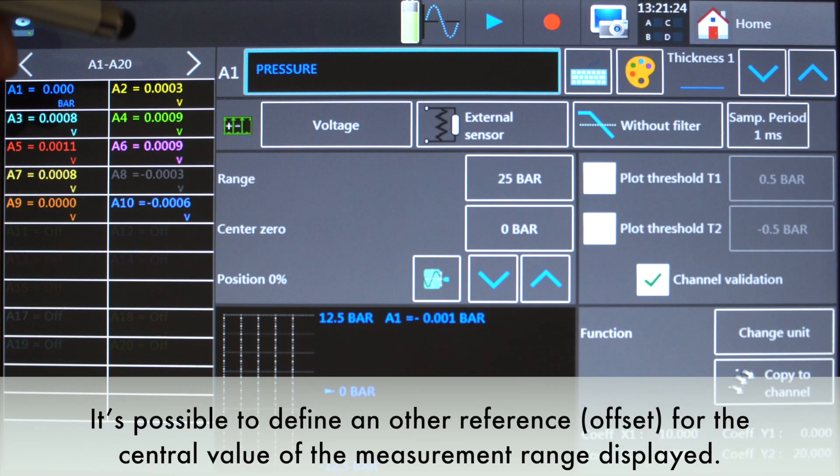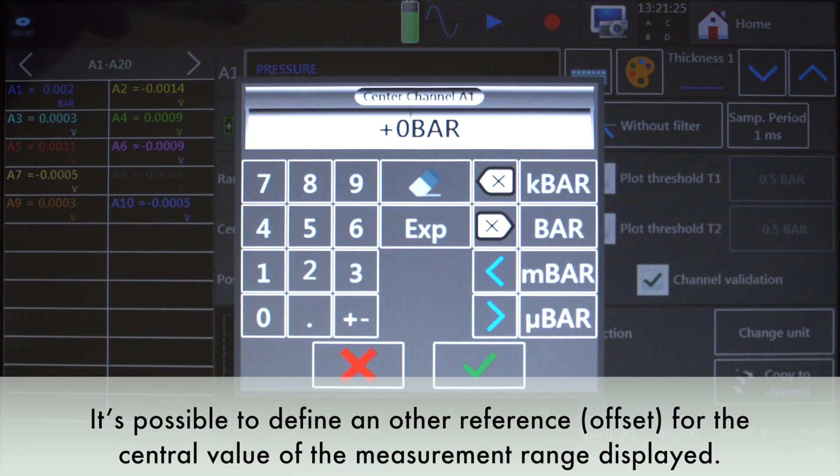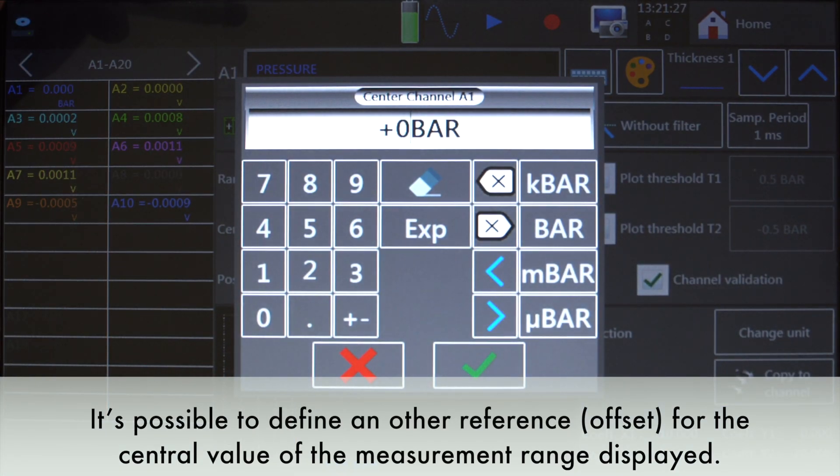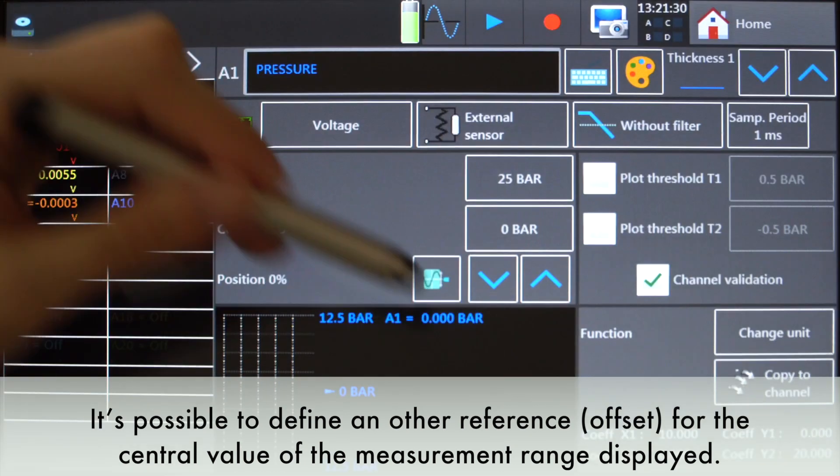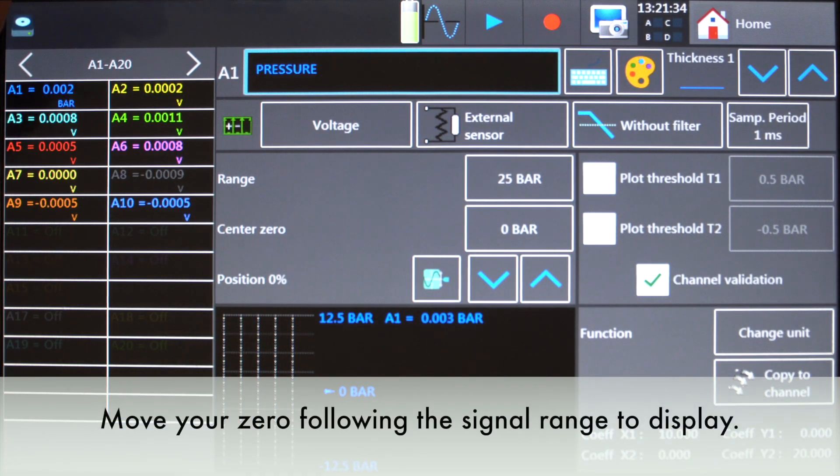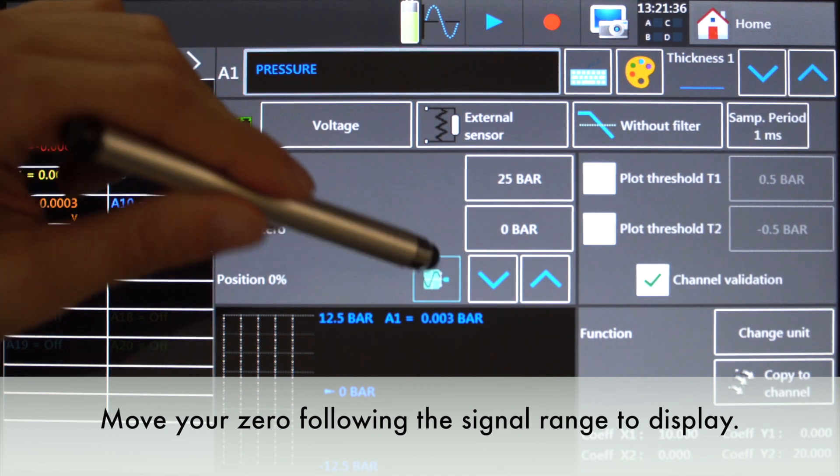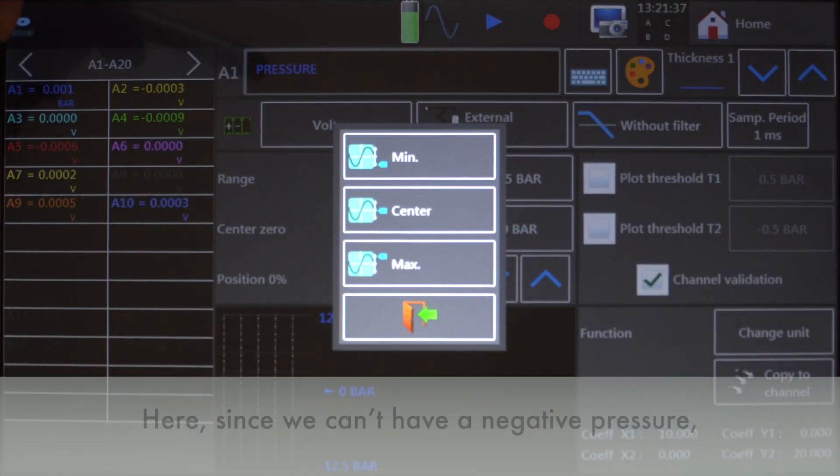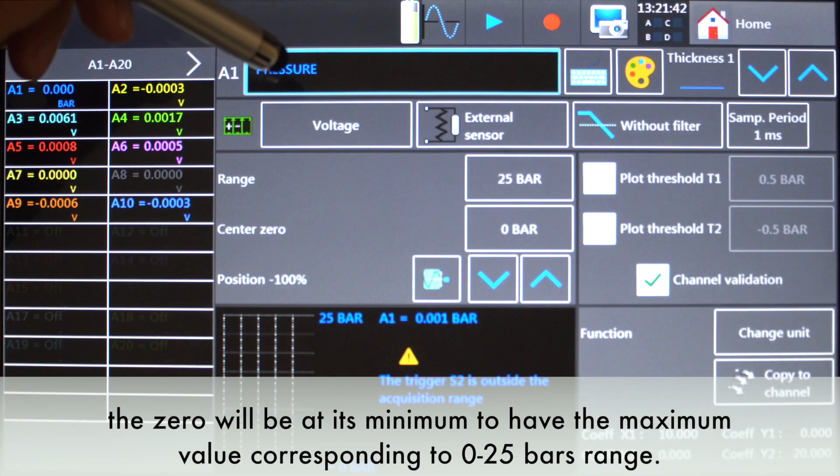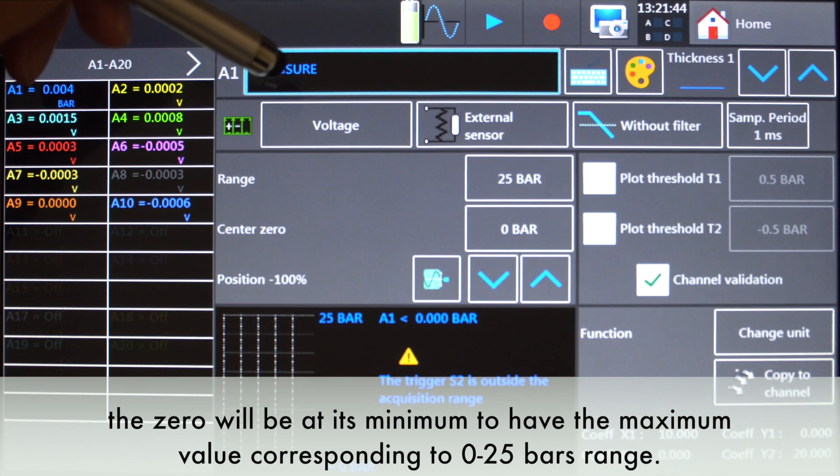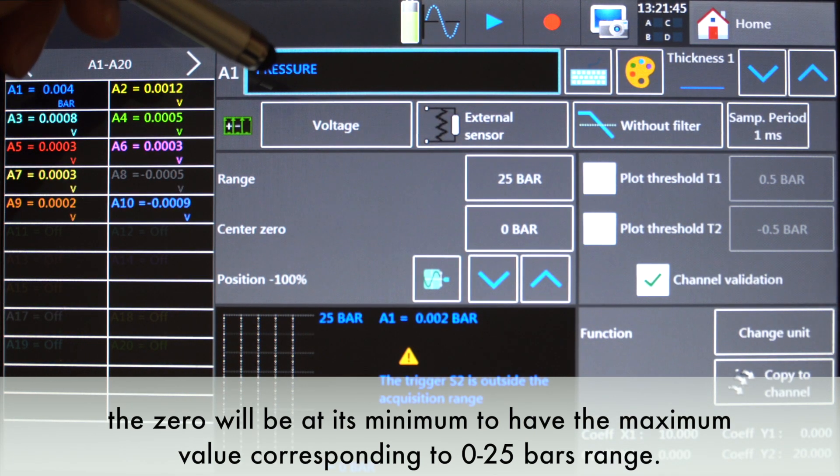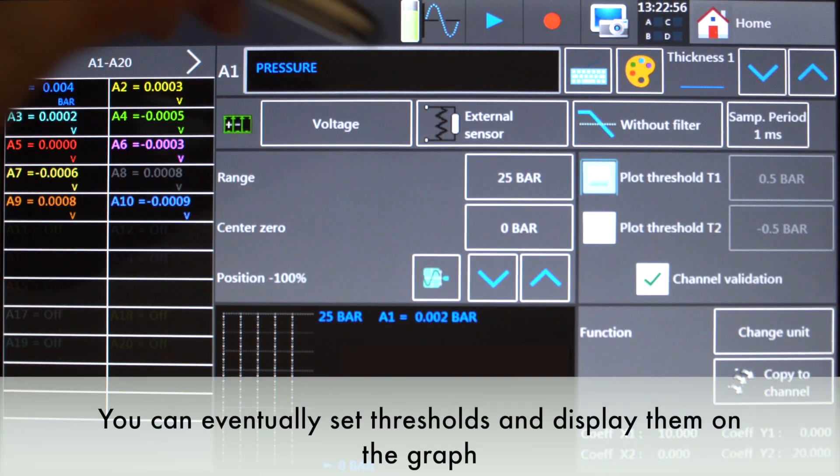It's possible to define another reference for the central value of the measurements range displayed. Move your 0 following the signal range to display. Here, since we can have a negative pressure, the 0 will be at its minimum to have the maximum value corresponding to a 0 to 25 bars range.